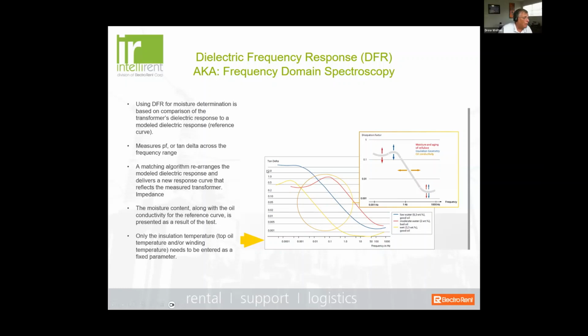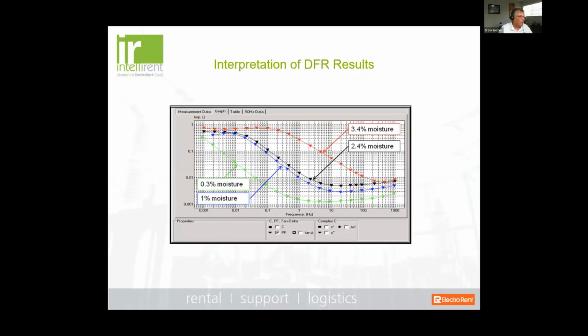So if you see here, what you'll see is your tangent delta measurement, and this is your frequency range here. And based on the geometry of the response of the curves, they could correlate that to the exact moisture content in the insulation. Now, to the naked eye, it may be difficult to look at this figure right here and say, well, how much moisture is that? Well, what's nice to know is that based on these algorithms, the software in these devices should be able to do this, or will be able to do this for you. So you can see the different responses. Okay, so we have a higher geometric response right here, which is 3.4% moisture, and that's problematic. 2.4%, as opposed to very low moisture content, 0.3, just based on the response that we get from this test.